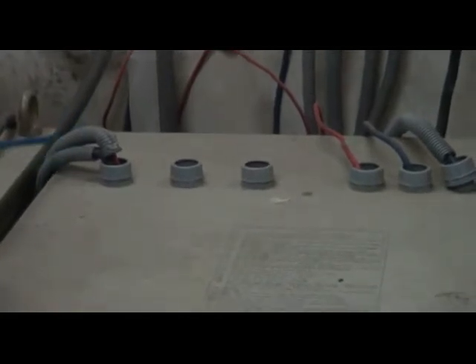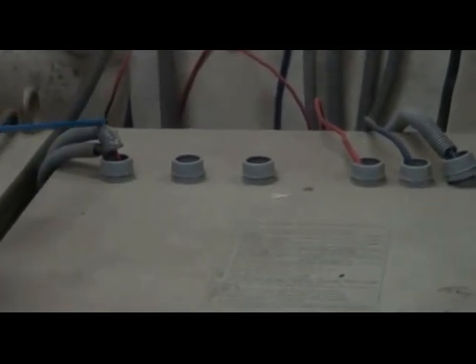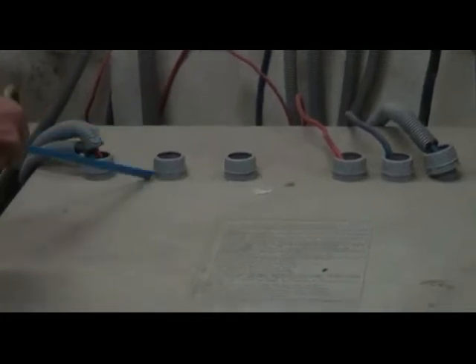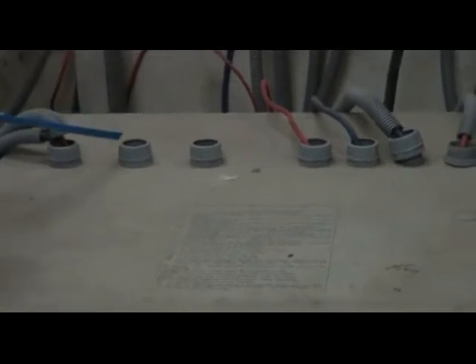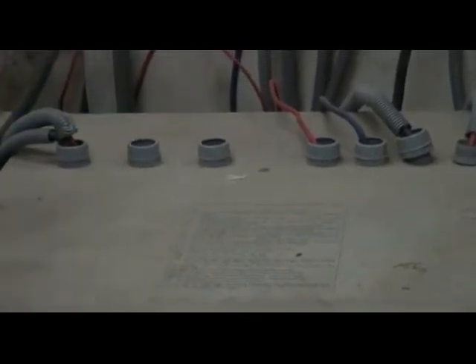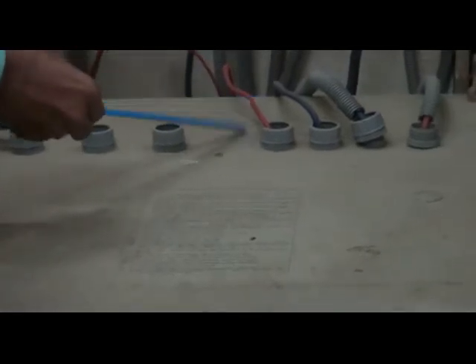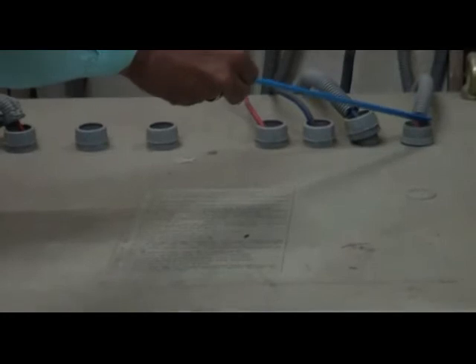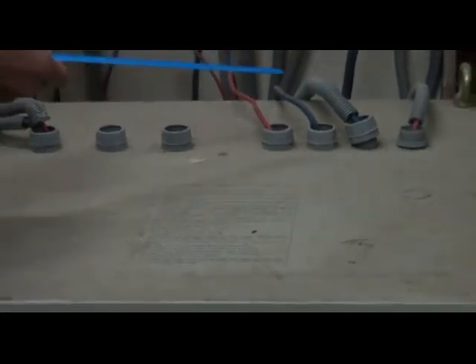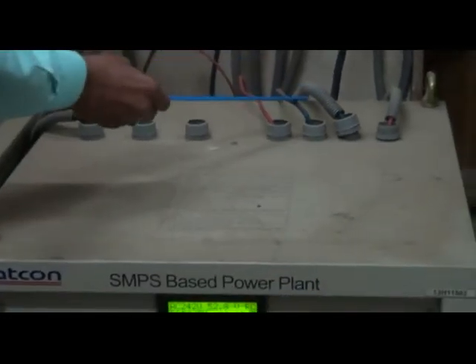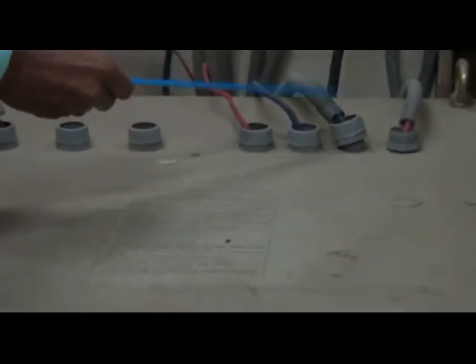The AC input, phase, neutral and earth for this charger is taken by a cable through top hole and terminated accordingly on AC terminal block. The positive wires of battery and load, normally red, and negative wires of battery and load, normally black, are also terminated on terminal block inside the power plant, positive to positive and negative to negative through top holes.